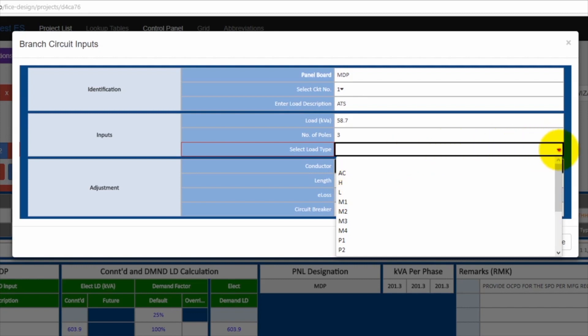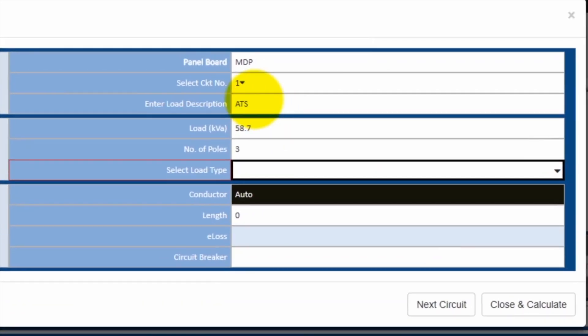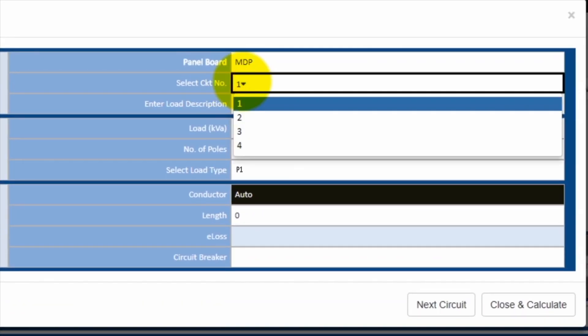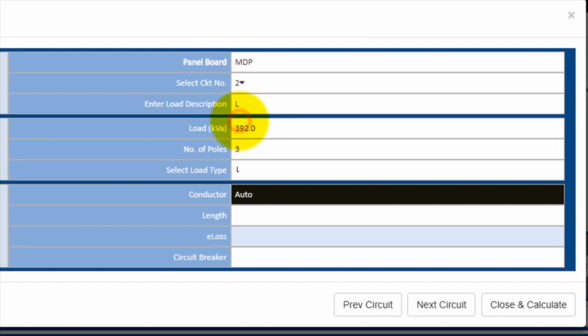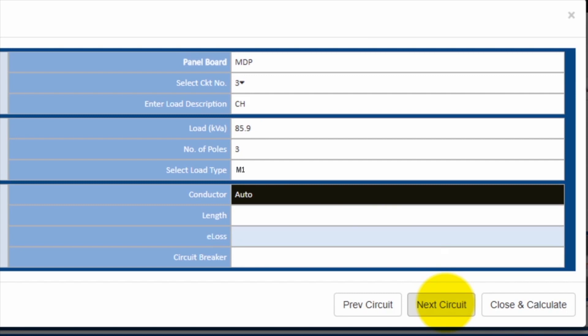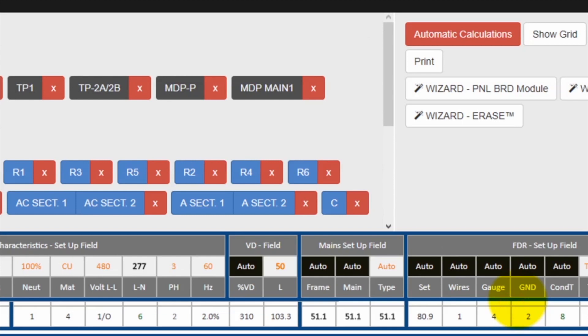Now if you scroll circuit by circuit, you can see that we have already input some values associated with this particular panel MDP. Right now we're looking at circuit number two with a load description of lighting and the load kVA is 392. You can go ahead and keep on going circuit by circuit until you're done with this particular panel. Then close and calculate.